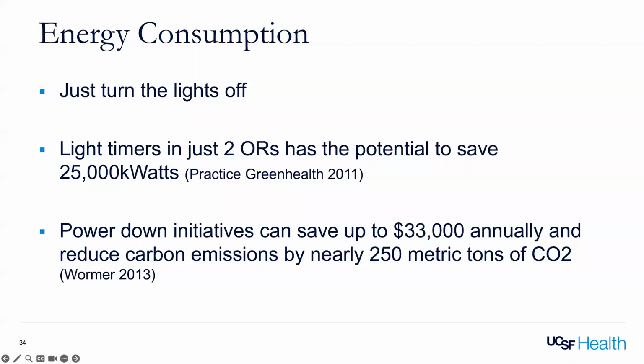A single hospital in Washington employed these timers for automatically turning off the lights in the operating room in just two of their ORs, which reduced their total electrical output by 25,000 kilowatts. It also resulted in savings of $4,000 annually per operating room where this was employed, which is particularly useful when talking to administrators about potential changes.